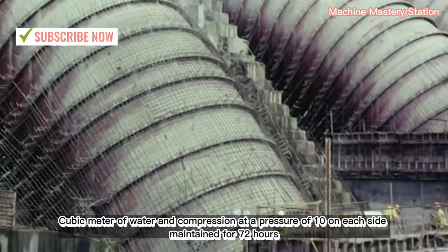According to the design calculation standards of the Moscow Institute of Hydraulics, the pressure pipe consists of modules welded together. After welding, each of these pipes would be pumped with 7 cubic meters of water and compressed at a pressure of 10 on each side, maintained for 72 hours.